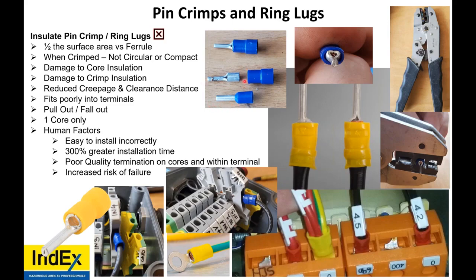There's the pin crimp with its insulation removed. It's half the distance. So more resistance. When crimped, it is not circular or compact, as per the standard. There's also damage to the core insulation. As you can see on the black here, it is misshapen. Unfortunately, when you use these crimpers, it crimps on the metal and the insulation because it can't do any other way. So it damages the core insulation, it damages the crimp insulation.